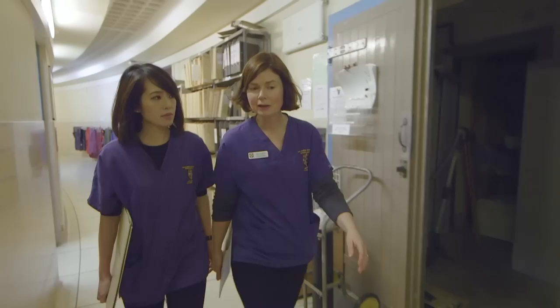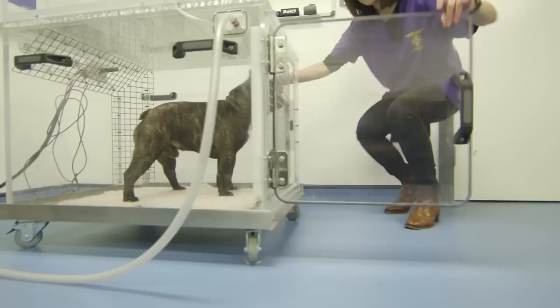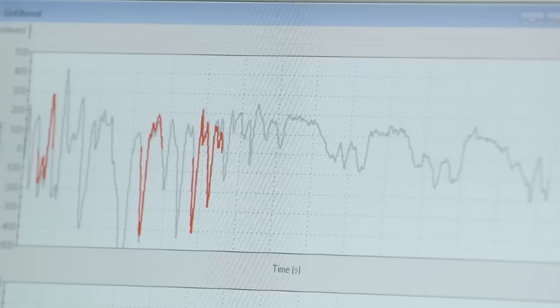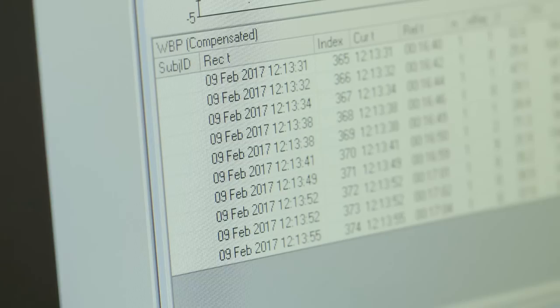The problem we've had from the beginning is trying to find a way of measuring this that's objective and consistent, so that you can measure a dog and come back six months later and measure the same dog again. I mainly developed a diagnostic test for BOAS that is totally non-invasive — we don't sedate the dog, we don't take blood, we simply put the dog into a chamber and the chamber tells us how severe the dog's breathing problem is. The pressure change signal is translated into respiratory parameters like tidal volume — how much air the dog can breathe in one breath — and other indicators of upper airway obstruction and what type of obstruction they have.